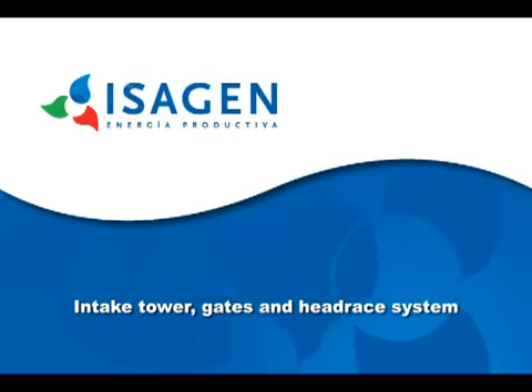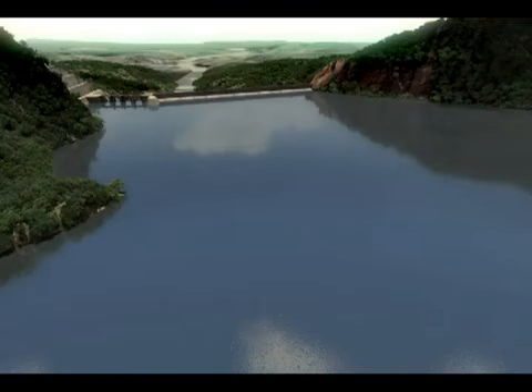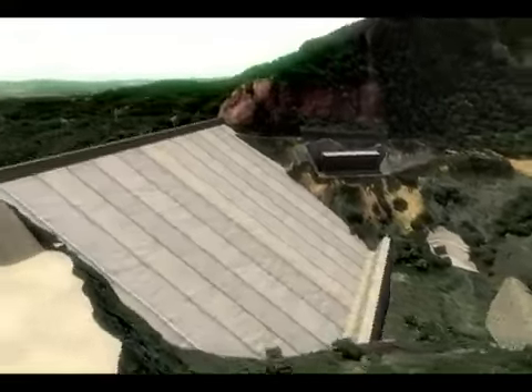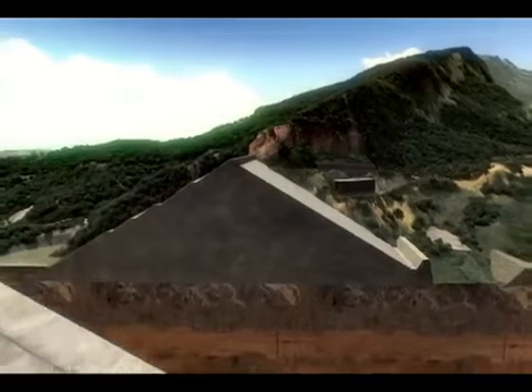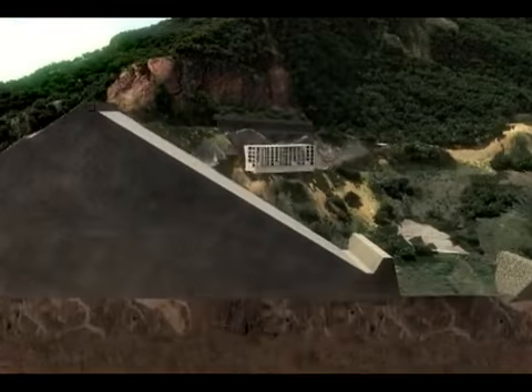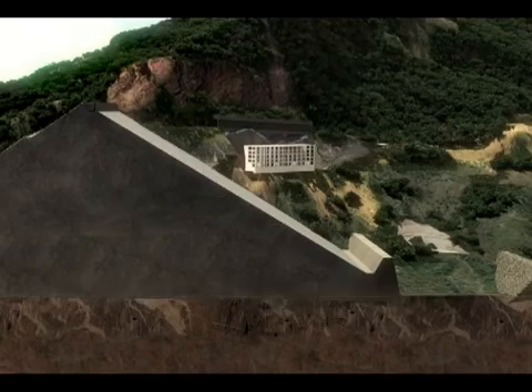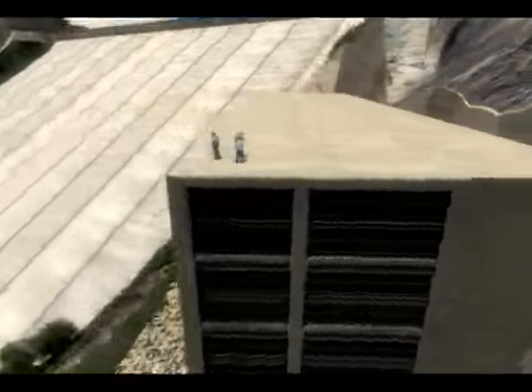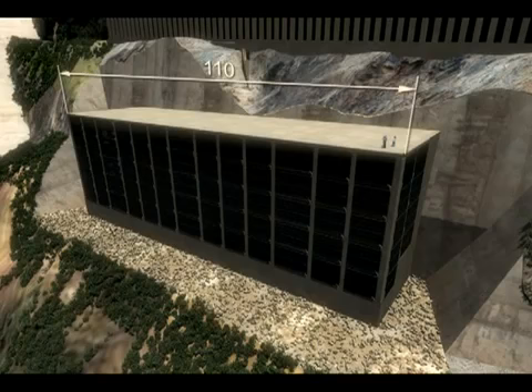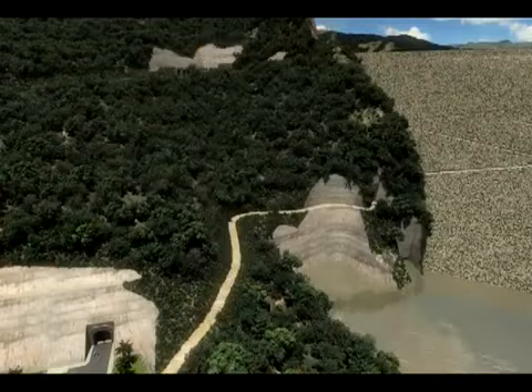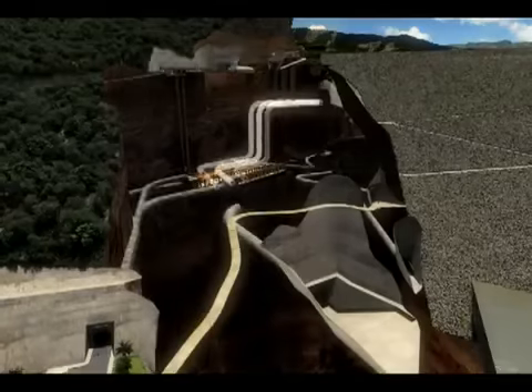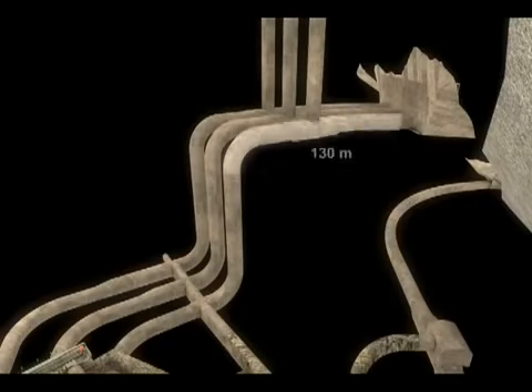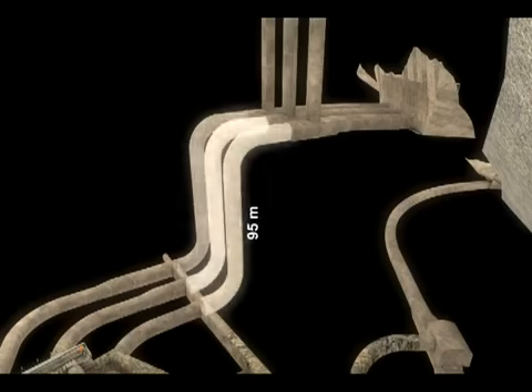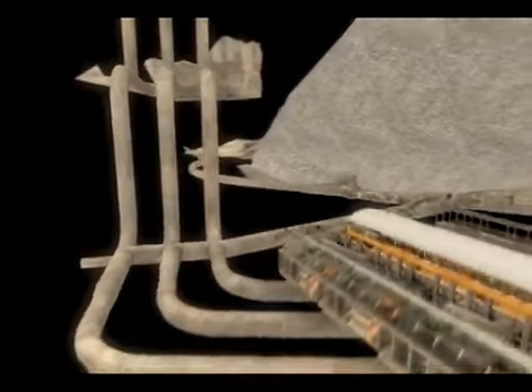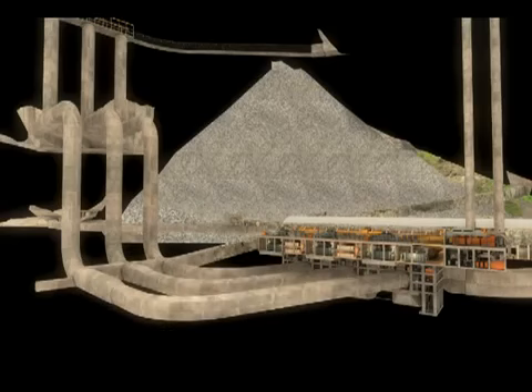Intake tower, gates and headrace system. Water stored in the reservoir reaches the generators in the underground power station through an intake located 90 meters above the riverbed. And that consists of a concrete structure with a 110 by 25 meter grid. The water then passes through 3 penstocks that consist of a horizontal section more than 130 meters in length, a 95-meter vertical shaft, and then the lower horizontal section more than 180 meters in length.